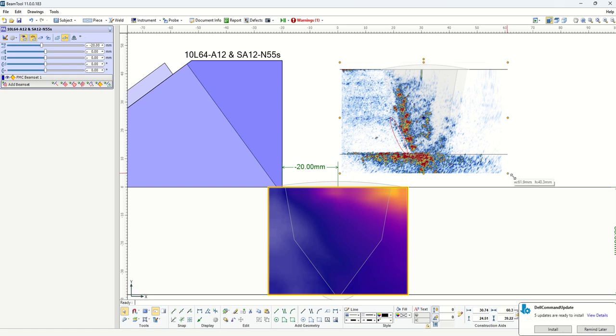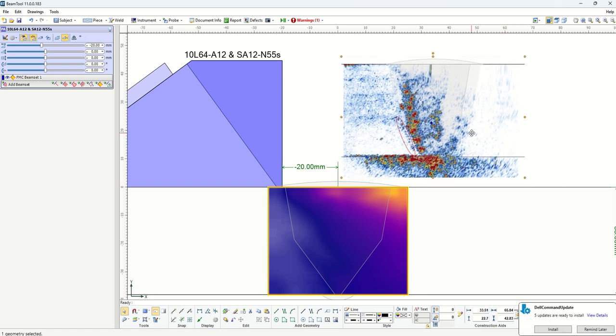And what we noticed was that parallel to the bevel, we have these tiny voids which are parallel to the bevel along the HAZ, which is basically a signature of creep voids. And as you know, what we were really careful about in designing this technique was that we have a uniform focal area and vertical resolution along the bevel, and that's what paid off. And it seems like we are sensitive to these, and we detected these ones.